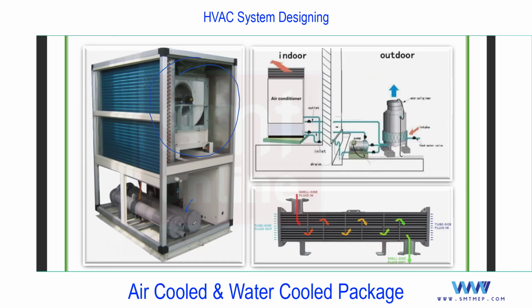You see, this side is the same as air cooled, but this condenser type is different. In the previous air cooled package, you will find the coil and fin type, that is the fin and tube condenser. But in water cooled, you will find the shell and tube type condenser. And remember, shell and tube type can be a condenser or an evaporator, and that concept you'll find in the chilled water system. So shell and tube is a heat exchanger.